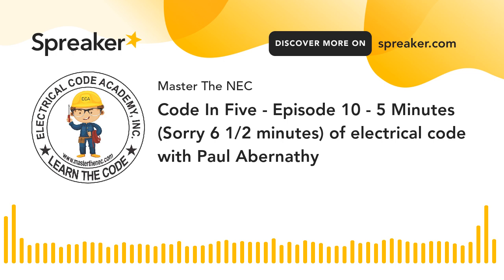So what is a temperature limitation? The temperature rating associated with the ampacity of a conductor shall be selected and coordinated so as not to exceed the lowest temperature rating of any connected termination, conductor, or device. Again, that is the weakest link theory.